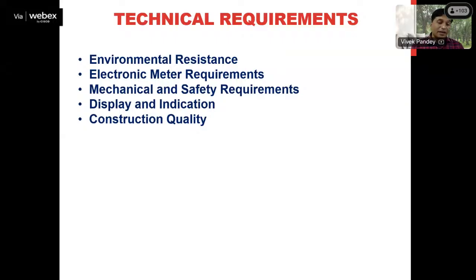Then the next requirement is related to voltage dip, surges, and electromagnetic interference. I have just discussed that in the previous case. The third one is that electronic components must be sealed and tamper proof. All the electronic components must be properly sealed and they must be tamper proof. Okay, this is another technical requirement. Then it should have a calibration memory, and the calibration memory should be of such type that it is protected from unauthorized changes. So there should be a calibration memory inside the measuring instrument.